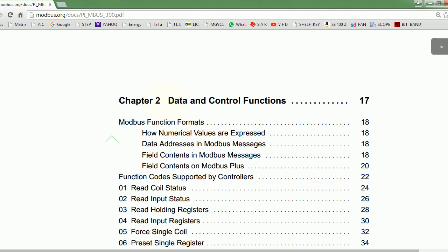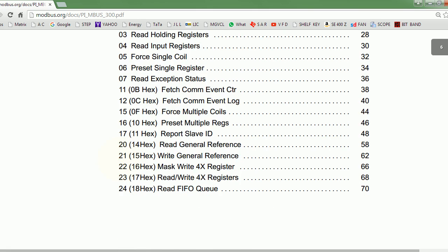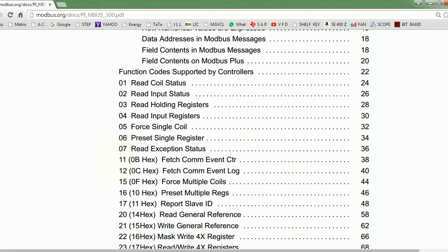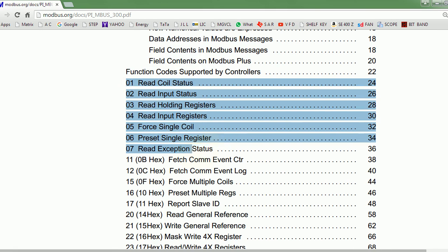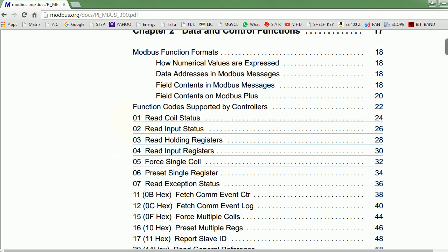There are a few Modbus data control functions which the master implements. You will probably have a master which has these functions already implemented. Function code 01 is the code for read coil status. A coil is a bit which you can set and also read - so it's a read-write bit. Function code 02 is for read input status. This is for digital input - it comes from the field. Some outside device writes this inside the PLC and then you can read it, meaning you cannot really set this bit yourself. This is like reading whether a limit switch was on or a sensor was activated.